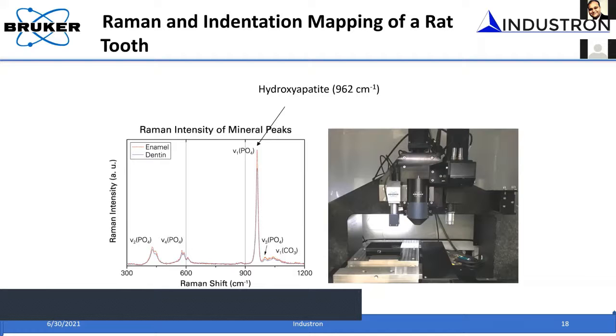This is what I'm going to show in this particular slide, where this has been done for a rat tooth. What we have done is basically you take a tooth material, cut and polish it, and put it on nanoindentation. This is a typical 950 or 980 nanoindentation. But along with this nanoindentation, if you look at this arrangement, you have a low load transducer, and then you have a high load transducer, then you have an optical microscope. In that optical microscope, you can combine Raman so that we can use it as a Raman microscope.